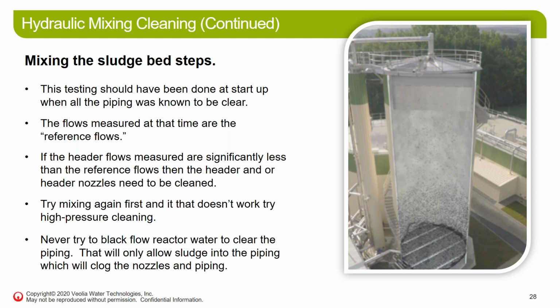If the header flows are much less than that benchmark or reference, then you're pretty sure you're starting to see some clogging in that header. So you can try mixing again, and try the header checks more often. Maybe those header checks clean it out and you see good flow, but then later it starts to deteriorate. You might have to increase the frequency of these header checks. If all that doesn't work, then you can try high pressure cleaning. If it gets so bad, you might have to take the system down, go into the system and really clean those headers out.